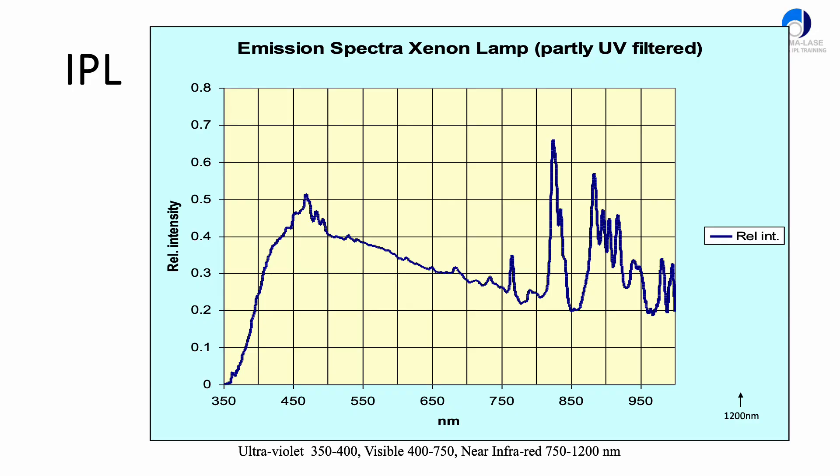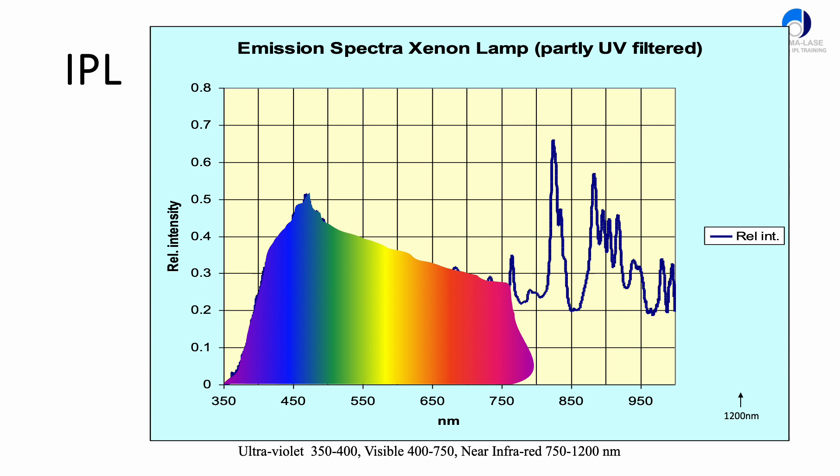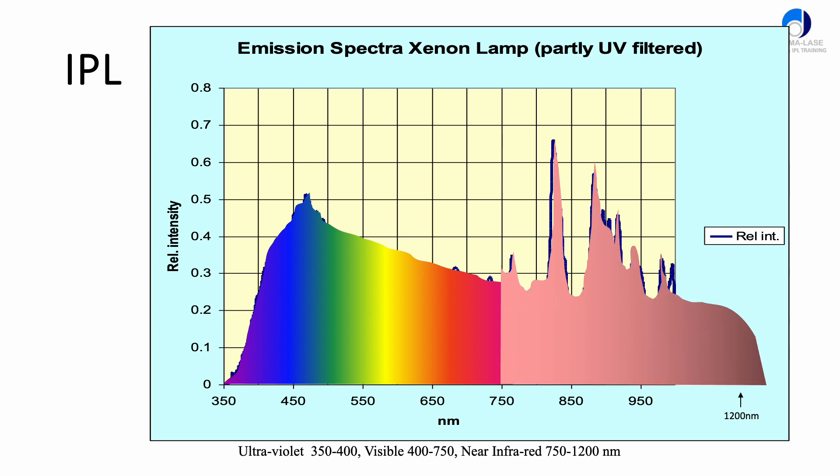If we look at the emission spectrum from an IPL system, this is the output from a Xenon lamp which is typically used in modern day IPL systems. We can see there's a lot of energy in the visible part of the spectrum from about 350 to about 750 nanometers, and then there's a big chunk of energy in the infrared part of the spectrum which is invisible to us and we tend to feel as heat energy. You can see there's a broad range of wavelengths here for a typical IPL device.